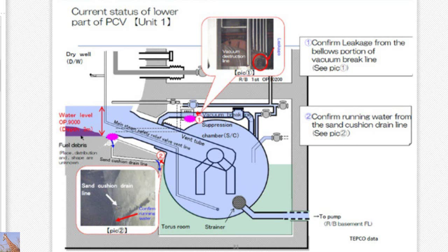This is only a guess for us — the water is leaking, meaning that the section above is damaged, which is highly possible. Therefore, this is a very big problem because if damaged, one possibility is that shell attack has happened — the debris in the PCV may be causing damage. So we have to take that into consideration for investigation. Next, this is unit number two. Using the vent pipe sleeve, sand cushion drain, and bellows, and a four-legged robot developed by Toshiba — leakage has not been detected, which is very different from unit one.